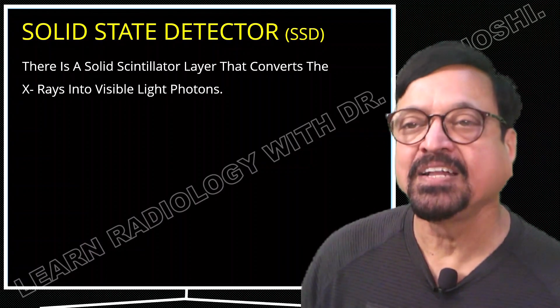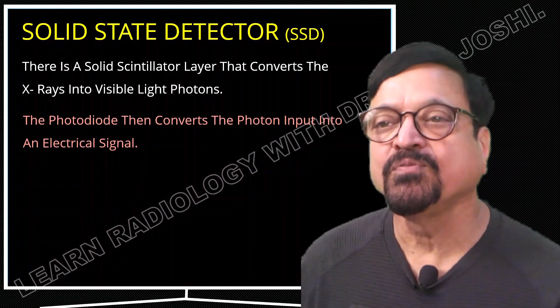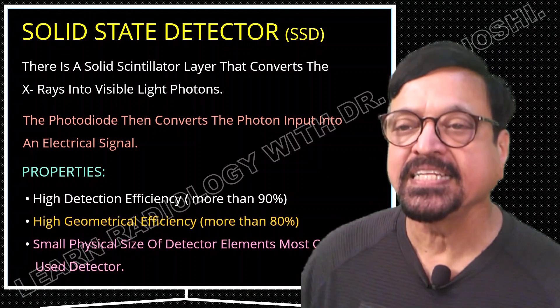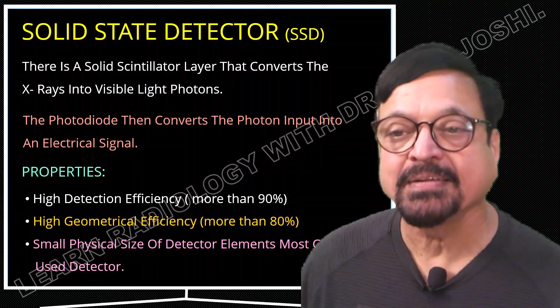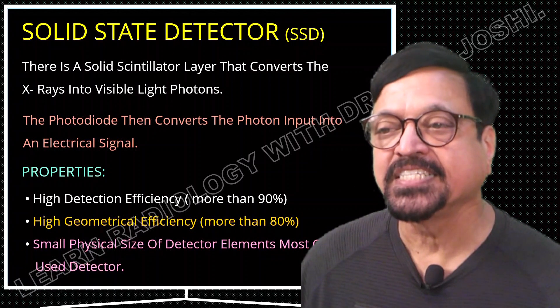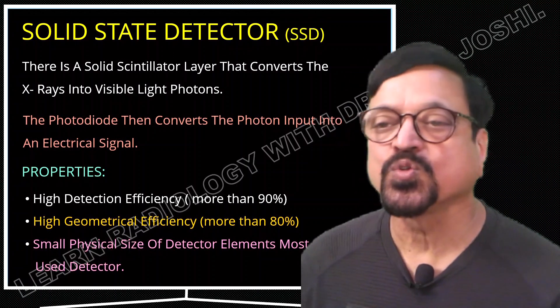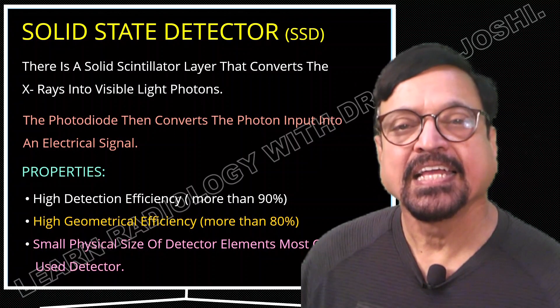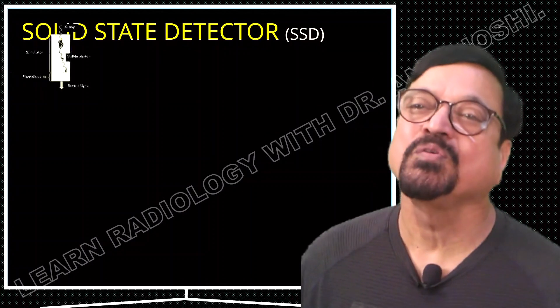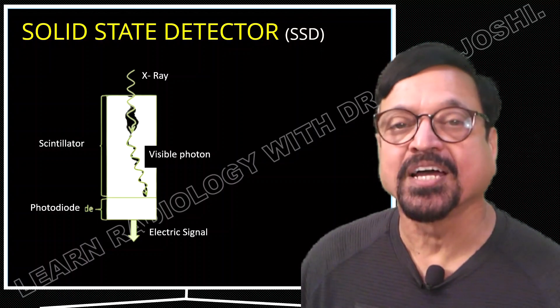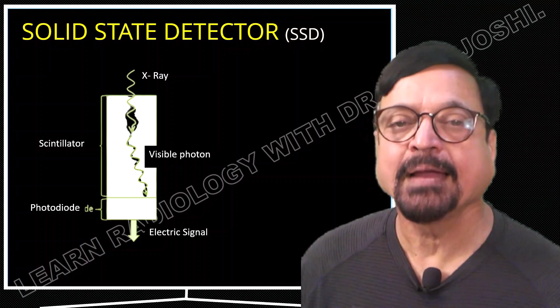There is a solid scintillator layer that converts X-rays into visible light photons. The photodiodes then convert the photon input into electrical signals shown on the monitor. These detectors have high detection efficiency of more than 90%, high geometric efficiency of more than 80%, and small physical detector element size, making them the most commonly used detector — due to their small size, high efficiency, ability to fit more in number, and economical cost.